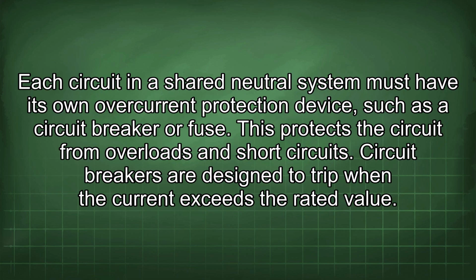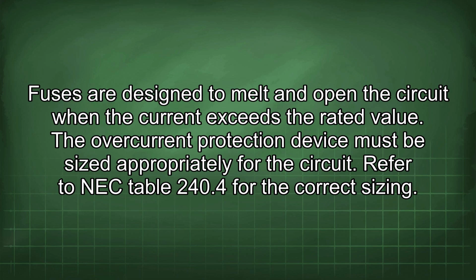Each circuit in a shared neutral system must have its own overcurrent protection device, such as a circuit breaker or fuse. This protects the circuit from overloads and short circuits. Circuit breakers are designed to trip when the current exceeds the rated value. Fuses are designed to melt and open the circuit when the current exceeds the rated value. The overcurrent protection device must be sized appropriately for the circuit. Refer to NEC Table 240.4 for the correct sizing.